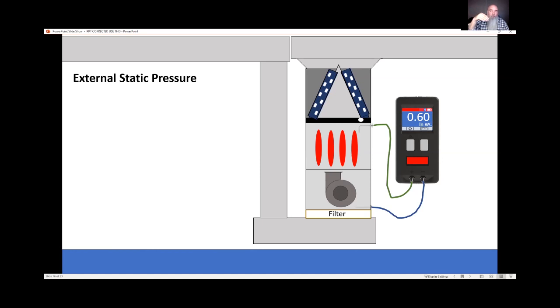Same comparison to the passive flow hood. If you're using a typical manometer that you would be using for duct pressures, stuff that's a 1/10 of an inch-ish or greater, a standard $100 digital manometer, when you start measuring the pressures that affect those combustion appliance products, we can end up with another random number generator. So the fact that this is what's required in the standard, again, I think it was a good move. What the original intention was, I don't know. And I think talking about this stuff lends more credibility when I really don't know the process behind what they chose. So it was a good move on their part.